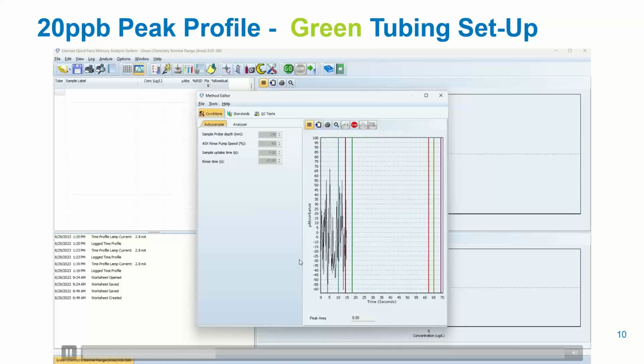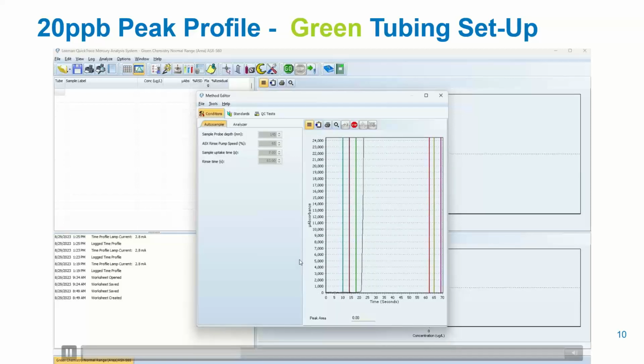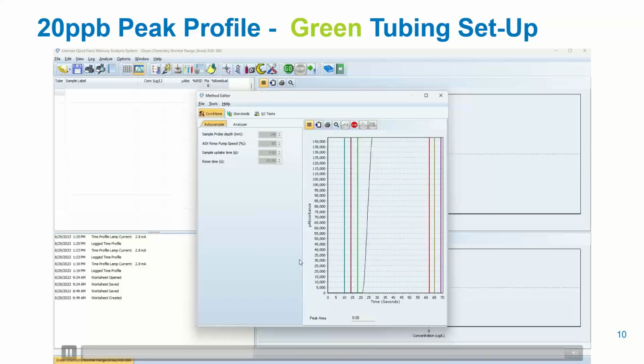The shape of this peak, you will notice, is different compared to the last profile. So since this is a peak area method instead of peak height, these are going to look more like a chromatography peak with a little bit of a tail, basically straight up, basically straight down, and then it'll rinse for the remainder of the 63 seconds. So take note of where the green and the red integration lines are. So the software is going to look at all of the data between those lines and compute the peak area. So coming back down to baseline. About 10 more seconds left.